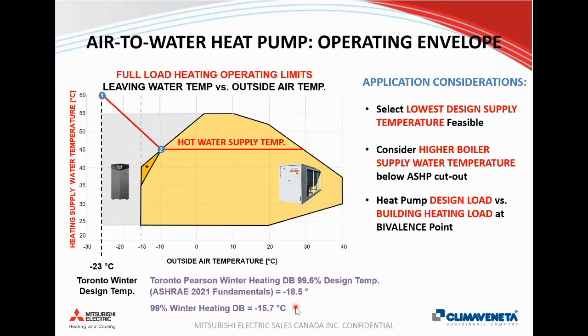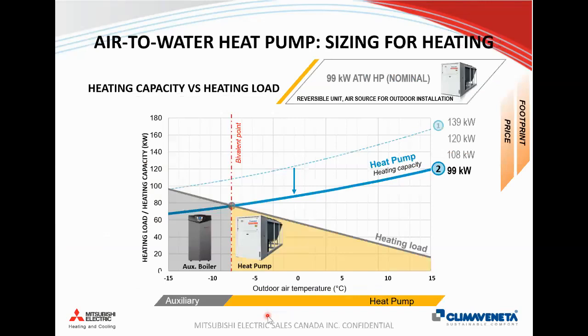So anyone dialing in from Toronto, it's been a pretty mild winter. Aside from the cold snap that we had over the Christmas break, we haven't really seen extreme cold temperatures, and it hasn't really been even below minus 10 for too much of the season. People often think that these heat pumps aren't really that useful to provide heat in the building because of the cutout temperature, but we'll see some weather data shortly that will show how that's not the case for certain climates. So the second thing that will change according to ambient temperature is the heating capacity.